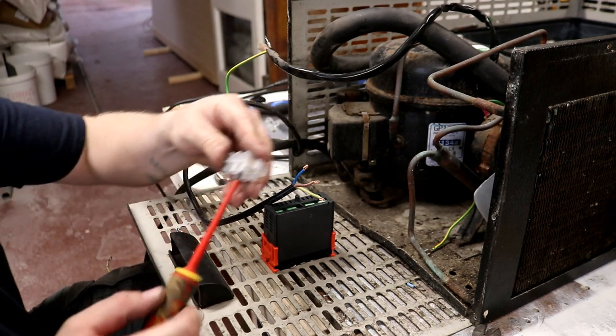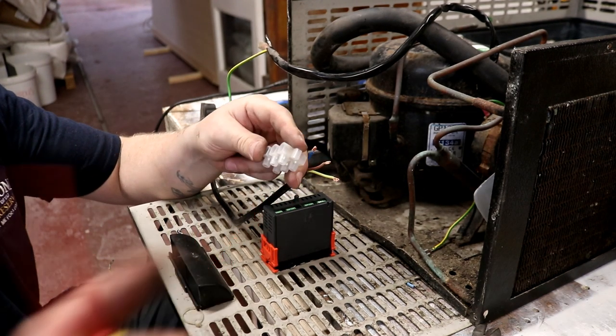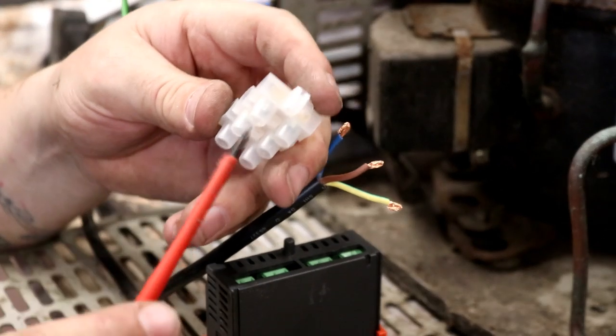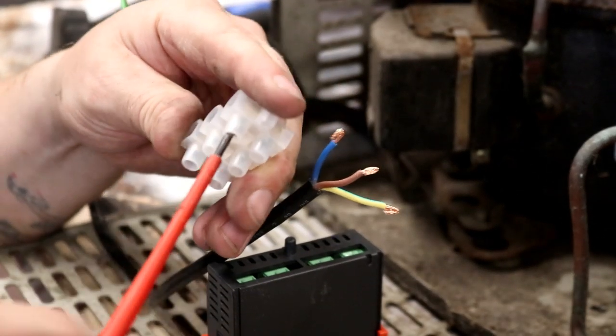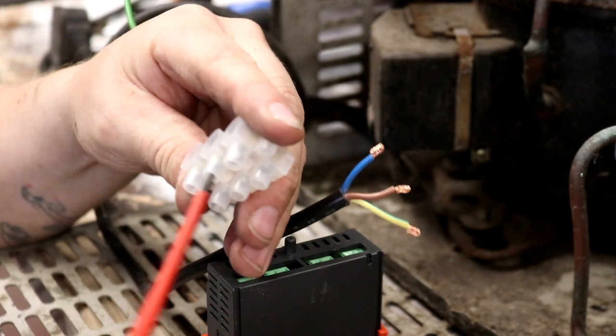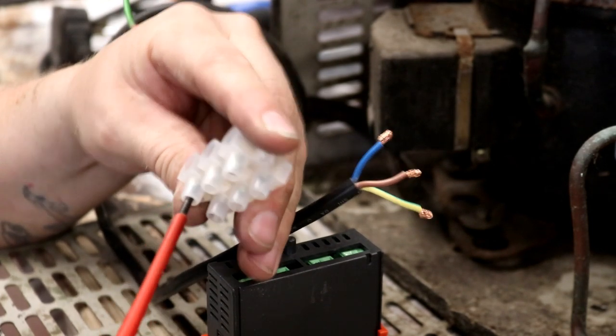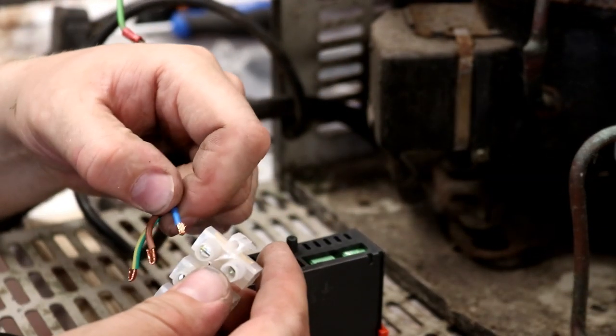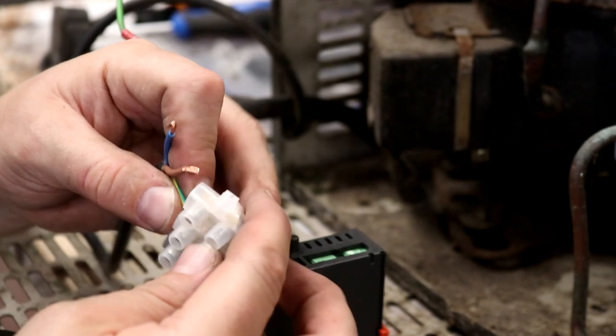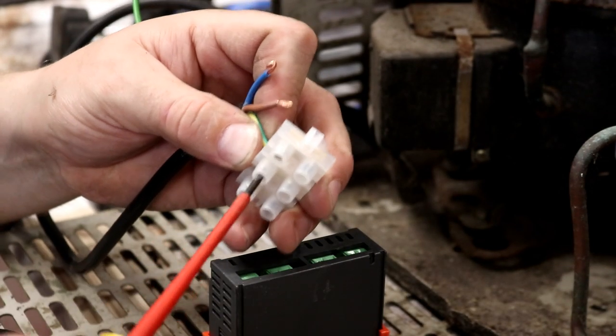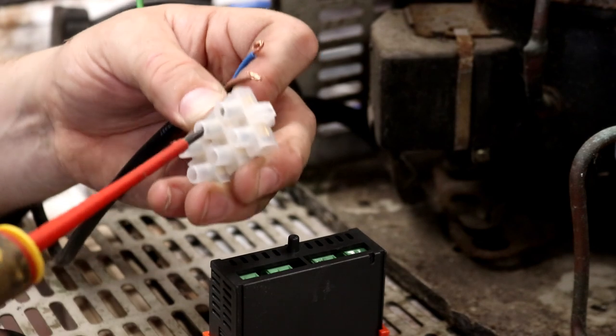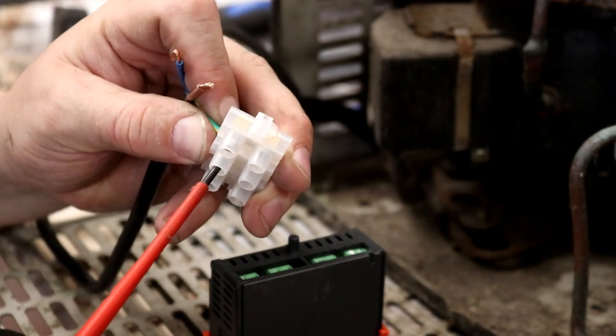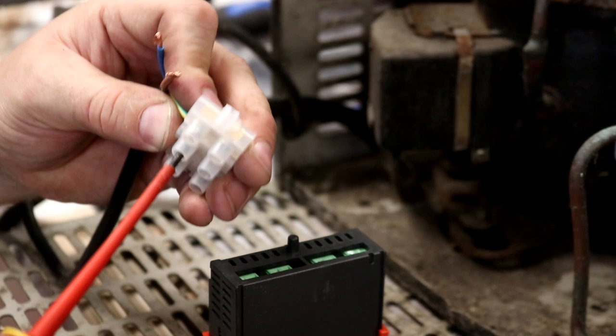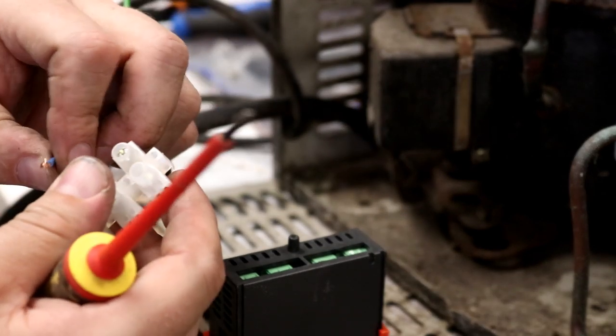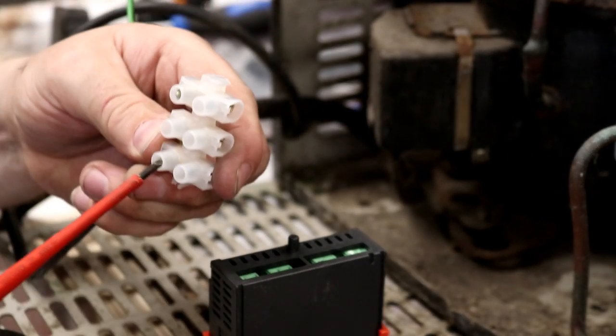We're going to wind out these three grub screws on the terminal block and pop in our mains feed. What I like to do is put the earth in the middle, which gives us a bit of a gap between the live and the neutral should you accidentally get any stray strands poking out the side of the terminal.